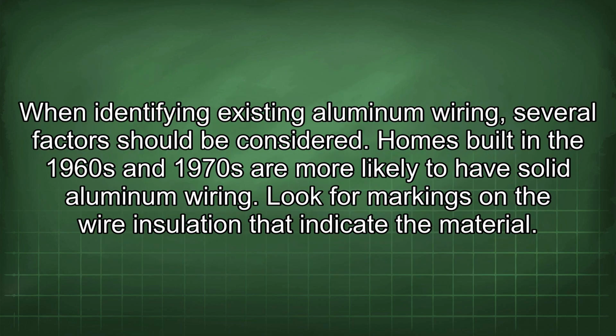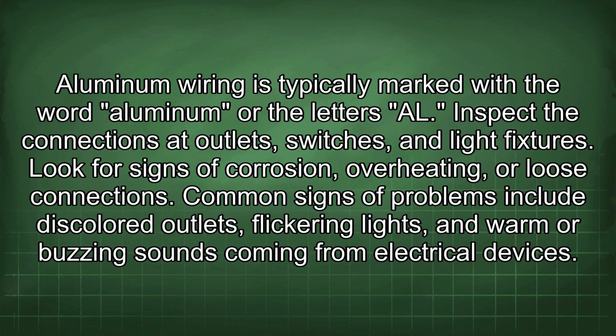When identifying existing aluminum wiring, several factors should be considered. Homes built in the 1960s and 1970s are more likely to have solid aluminum wiring. Look for markings in the wire insulation that indicate the material. Aluminum wiring is typically marked with the word aluminum or the letters AL. Inspect the connections at outlets, switches, and light fixtures. Look for signs of corrosion, overheating, or loose connections. Common signs of problems include discolored outlets, flickering lights, and warm or buzzing sounds coming from electrical devices.